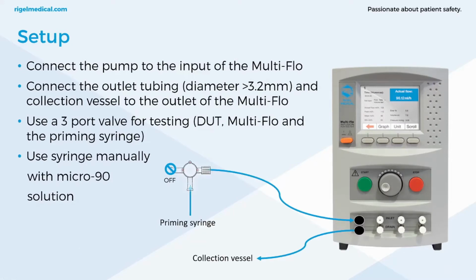Setup. Okay, so we connect the pump to the, sorry, that's incorrect. We connect the pump really to the T-piece. So you're going to use a T-piece or 3-port valve for testing. This is really crucial. So you've got your device under test on one, your Multi-Flo on another, and then the priming syringe on the other part of the port.